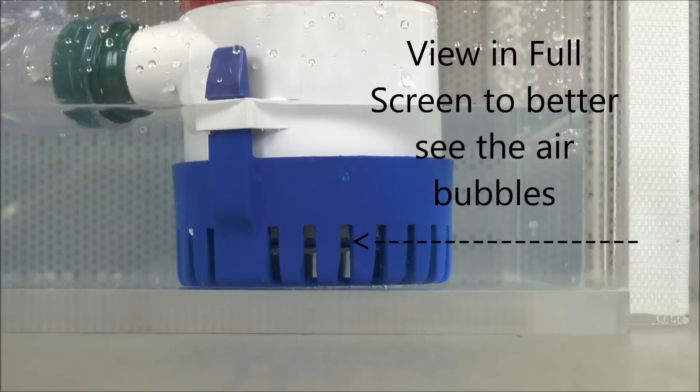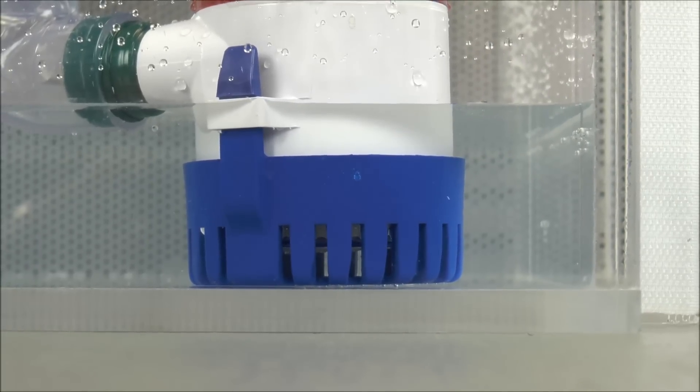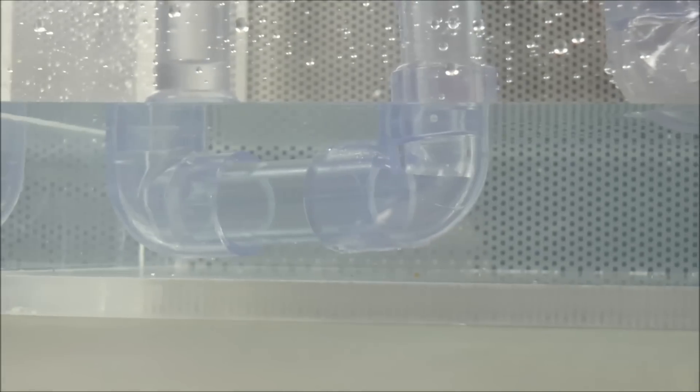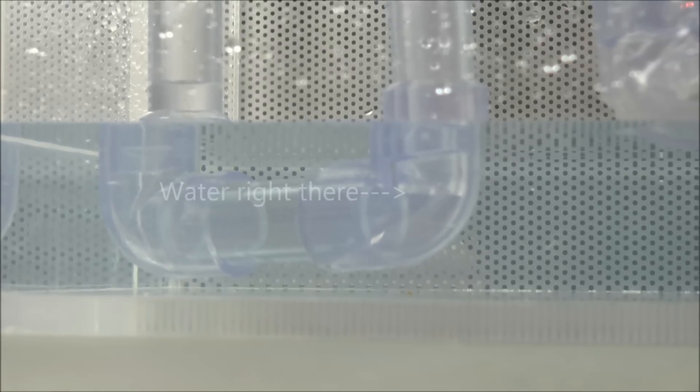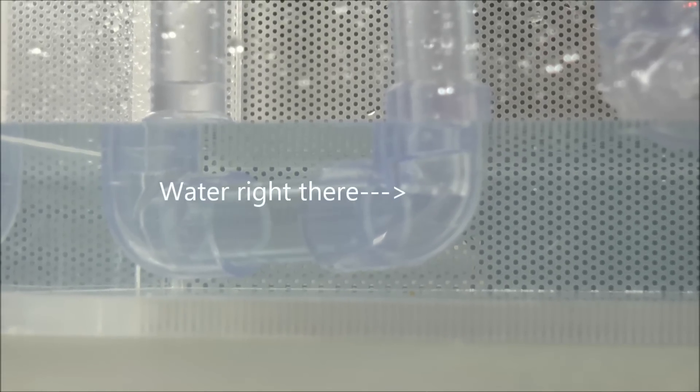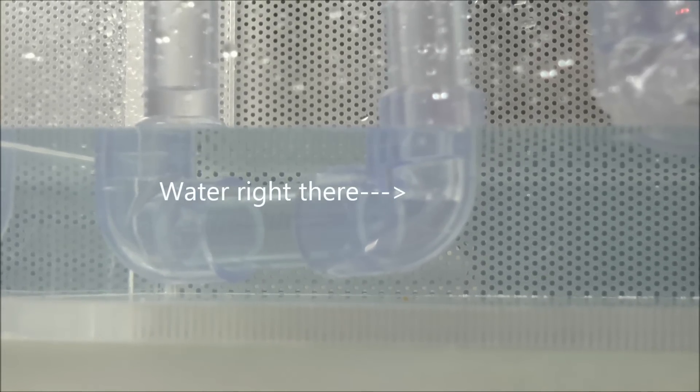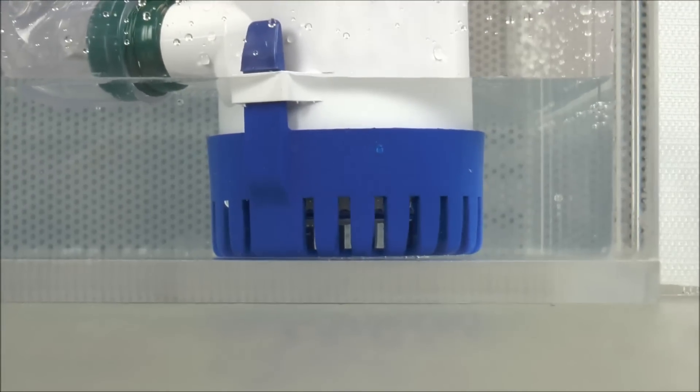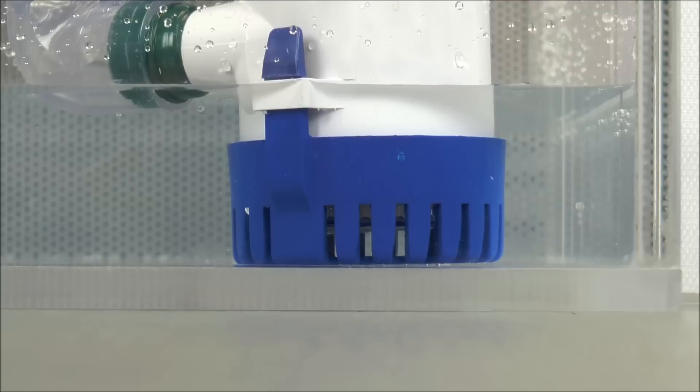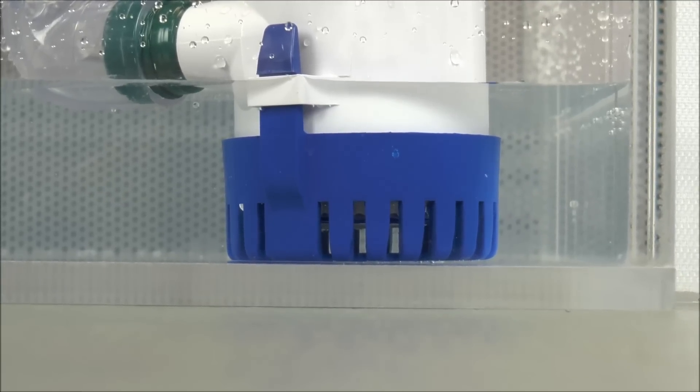That air cannot move through the system because of that trap right there. That water's got it stuck. It can't push through the system because of that valley. Gravity's pulling that water down to the bottom of that little valley there, and this air can't go any place.